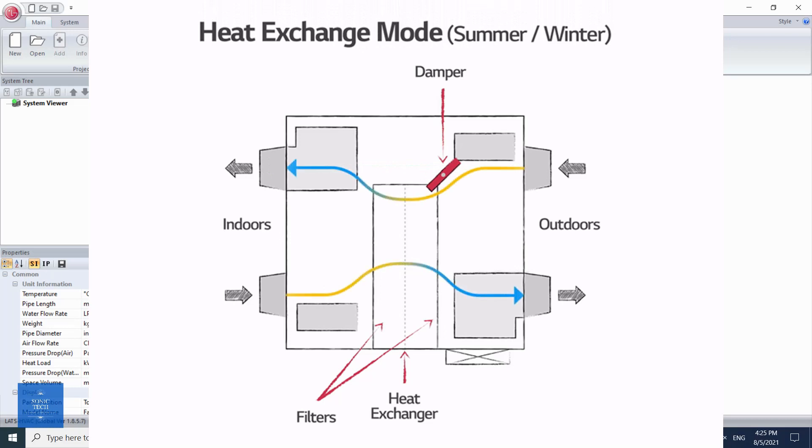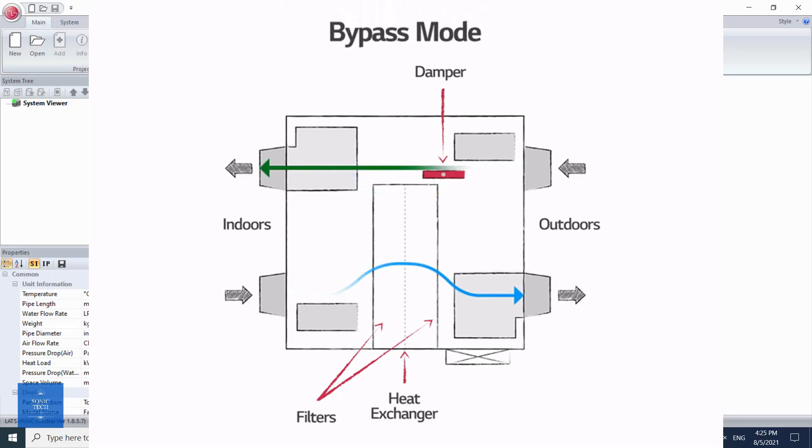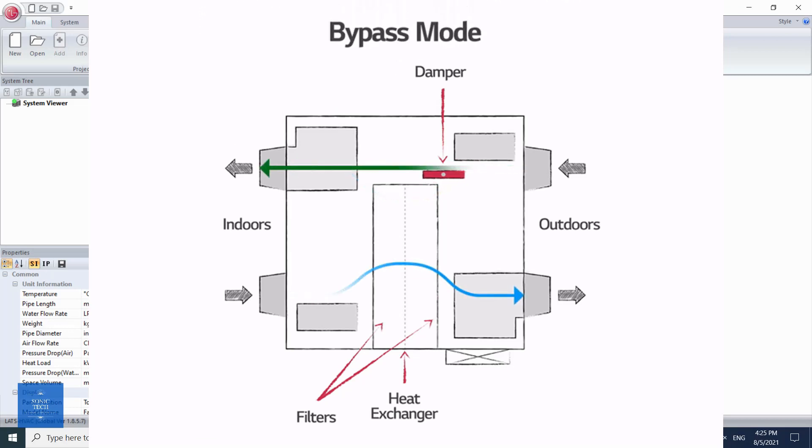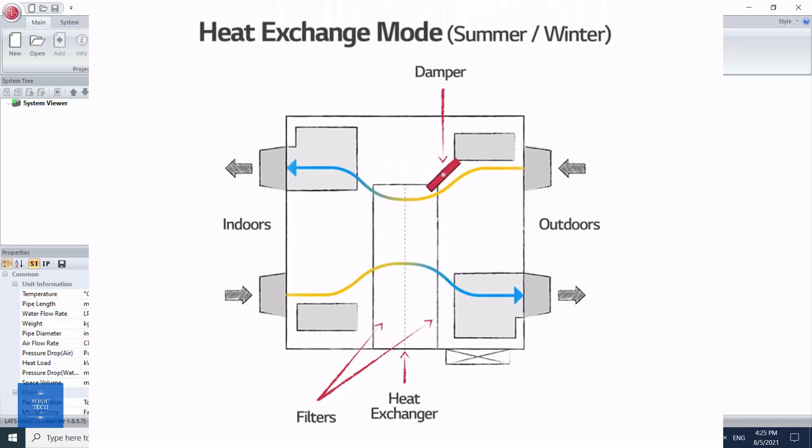ERV reduces the electricity consumption of HVAC systems, while improving indoor air quality. ERV is based on air-to-air heat exchange, using a spinning wheel or a stationary core where air streams can exchange energy without mixing.